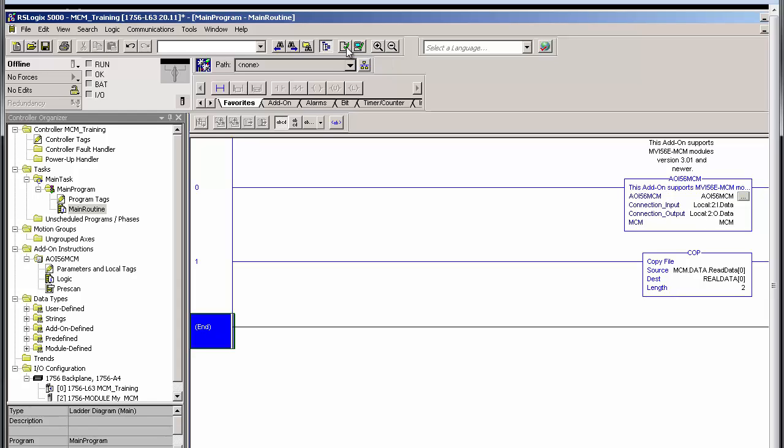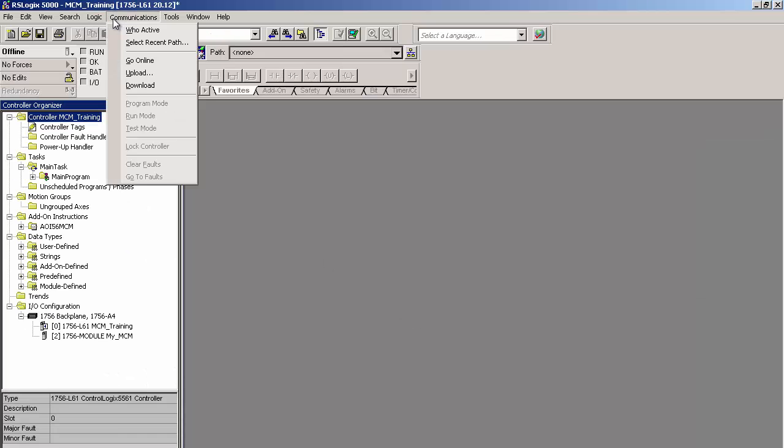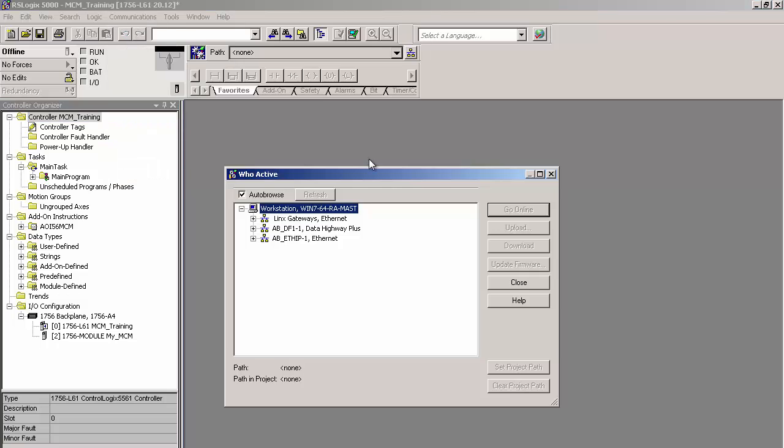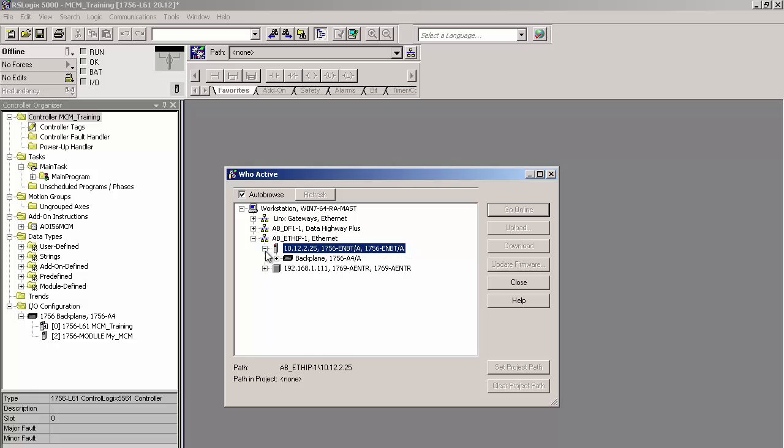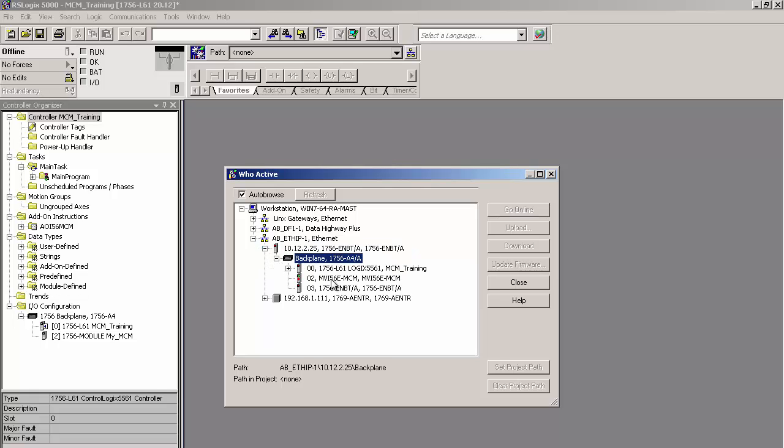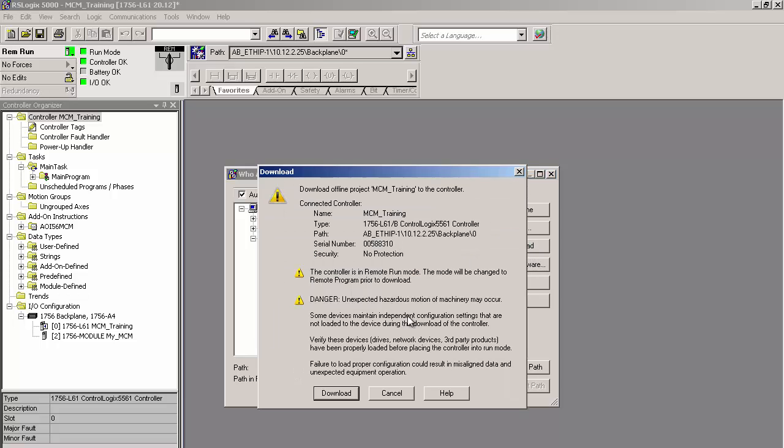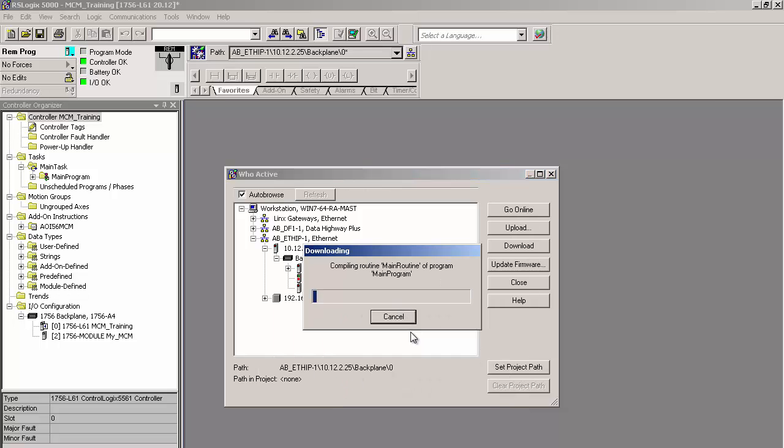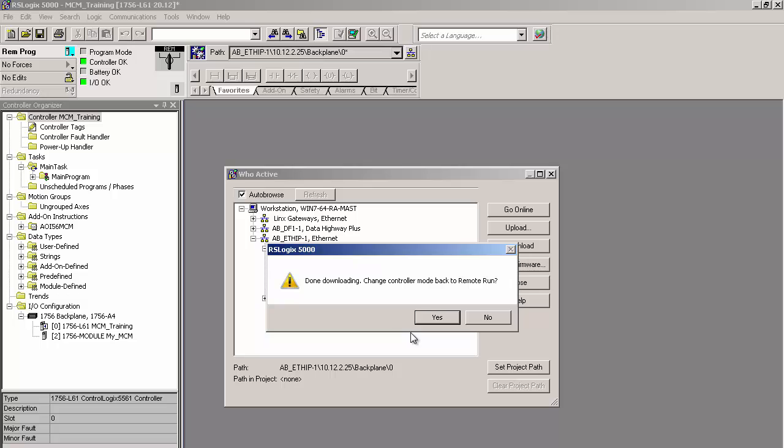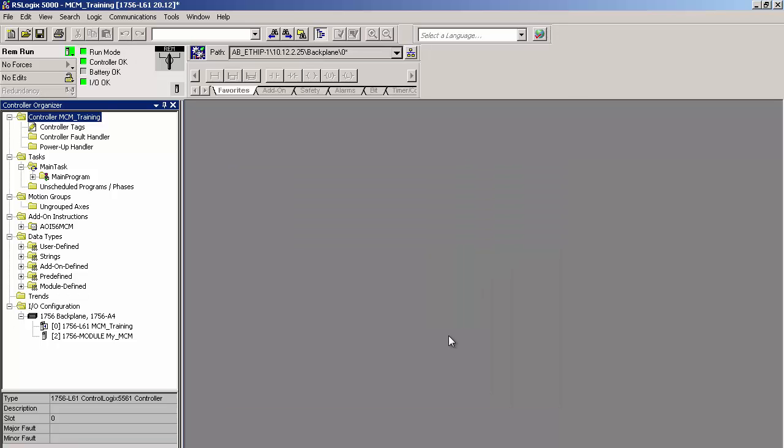So we should be ready to download the configuration to the processor now. I'll go up to communications, select who active. On the screen, I'll look in my Ethernet connections, locate the Ethernet module in the ControlLogix rack. I'll open up the backplane and select the processor and click download. And then click download again on the download screen. And once the download is complete, we're given the option to go online. We'll do that.